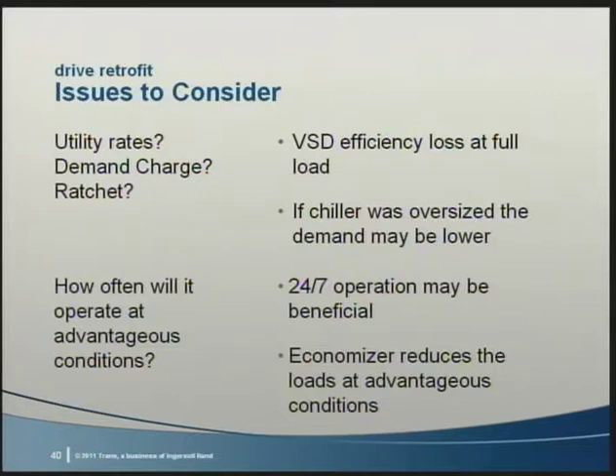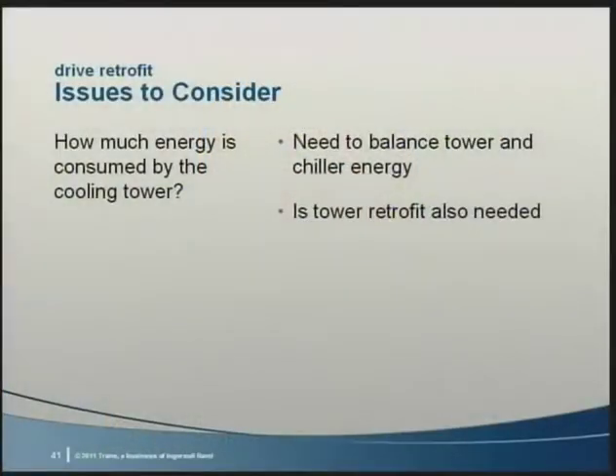Now next, are there enough hours when the lift is reduced and operating conditions are advantageous for the drive use? If the system is equipped with an economizer, the available hours that would be used for calculating the drive savings will normally be decreased. We also need to remember that lower cooling water temperature is not free. Additional tower fan energy is necessary to produce that lower tower water temperature and should be accounted for. Another option would be applying a VSD to the fan tower motor. We'll touch on that later.